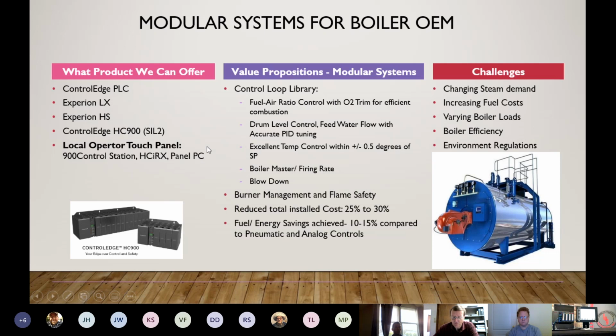ControlEdge HC900, obviously SIL2 for the burner management system, and then a local operator interface that you can attach to the HC900 to be able to look into the process. When we're looking at some of the pre-built function blocks that you could tie together to accomplish different control loops, we talked about fuel air ratio with O2 trim, drum level control, feed water, excellent temperature control. You can get pretty accurate temperature control, plus or minus 0.5 degrees.